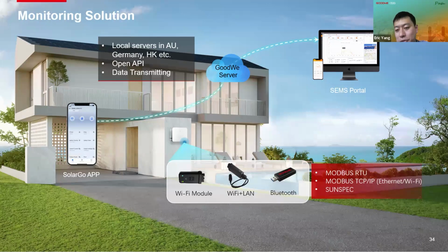And also, if the customer does not want to use the GoodWe platform, the GoodWe SEMS portal, they can also get the data from the GoodWe server by using Open API or data transmission. And except for this, the GoodWe inverter also follows some protocols, such as Modbus RTU, Modbus TCP/IP, and also SunSpec, which means if the customer has a local EMS device, it can control the inverter by these protocols.